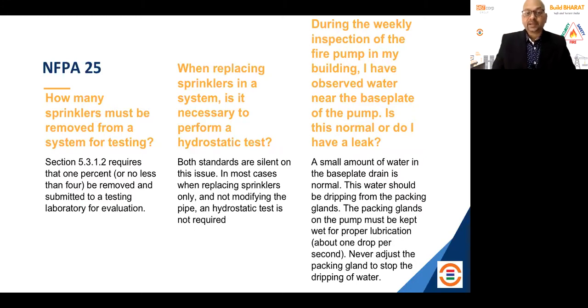When replacing sprinklers in a system, is it necessary to perform a hydro test? Like you have a fire accident, you have activated say 20 sprinklers, you remove those 20 and replace them with new ones. The question may come, do you still need to hydro test it? There is no clear-cut answer, which neither NFPA 13 gives nor NFPA 25 gives. It is up to your jurisdiction.